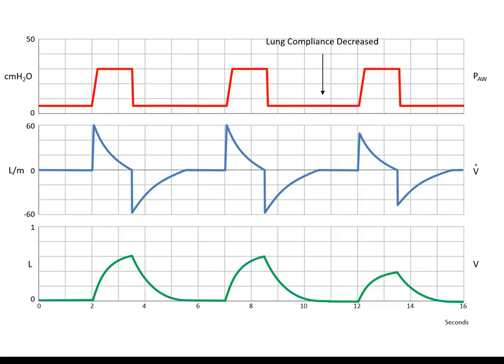In contrast to volume control mode, pressure control mode of ventilation will deliver a set pressure. That set pressure will result in a tidal volume that is dependent on the respiratory system resistance and compliance. Notice the difference in the flow waveform — it was a square wave in volume control, but in pressure control it is a decelerating waveform. If lung compliance decreases in pressure control mode, the machine will deliver the same set pressure, resulting in a lower tidal volume based on the equation of motion.